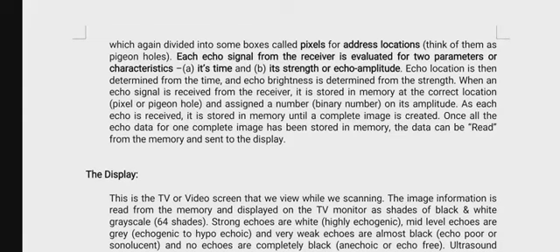So when the correct location of pixel, well, it is stored in the memory at the correct location and pixel, that is a pigeonhole, and assigned a number, what we call the binary number in computer language, on its amplitude. So every amplitude receives a binary number. As each echo is received, it is stored in memory until a complete image is created. Once all the echo data for one complete image has been stored in memory, the data can be read from the memory and sent to the display.